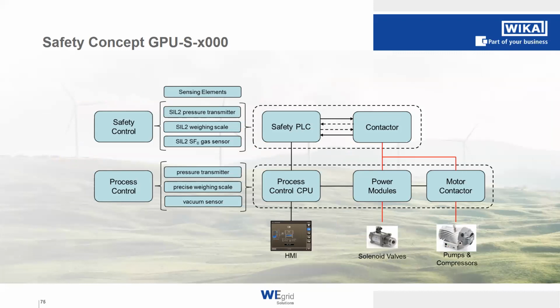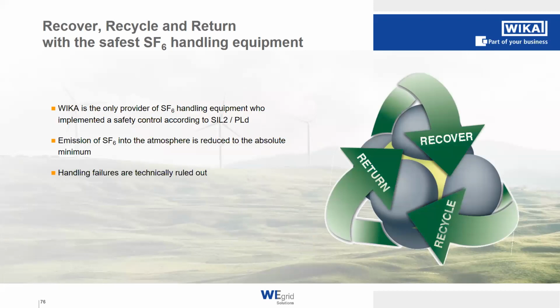To create a full safety concept and a safety function, we have a safety control which is working in parallel to our process control. With the safety control, we are rechecking all the data the process control is handling. And if the safety control recognizes a value which is unsafe and uncertain, it will shut down the process control and seal the necessary valves or stop the necessary components from working. WEGrid is currently the only provider of such an SF6 handling device which has SIL2 components within. And with that usage, the emission of SF6 is technically reduced to the absolute minimum.